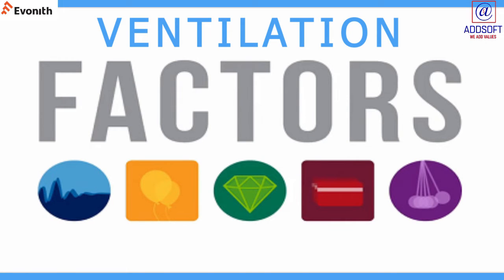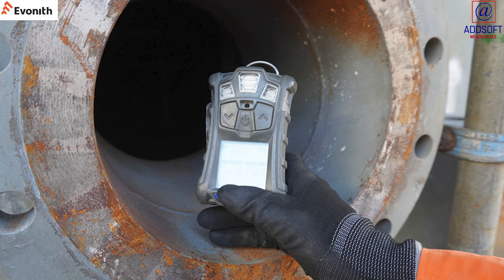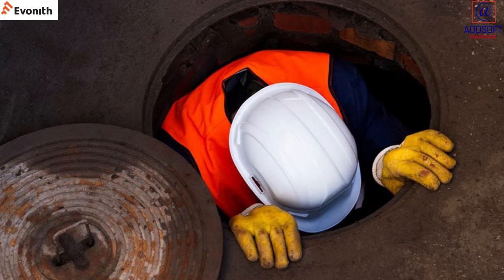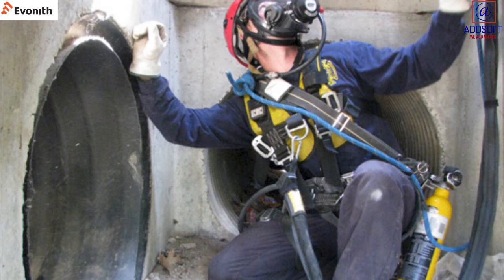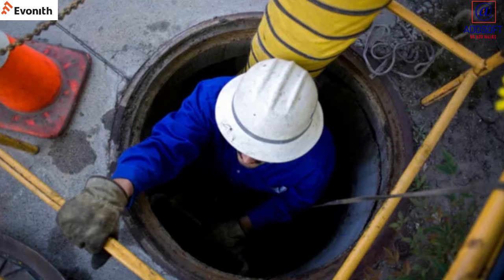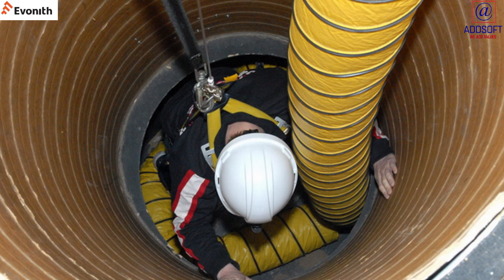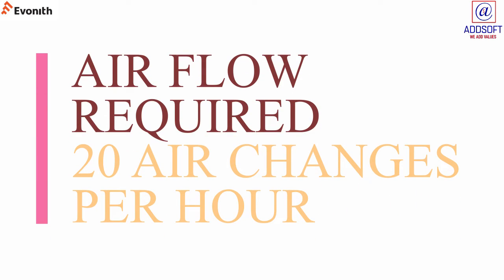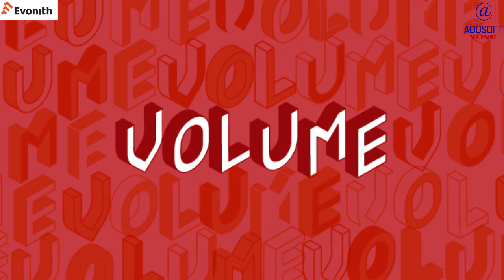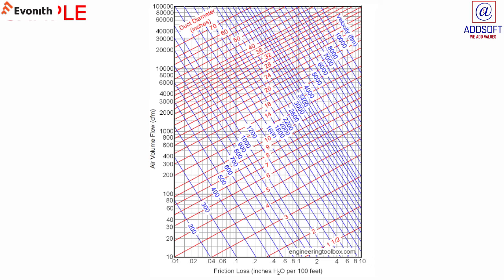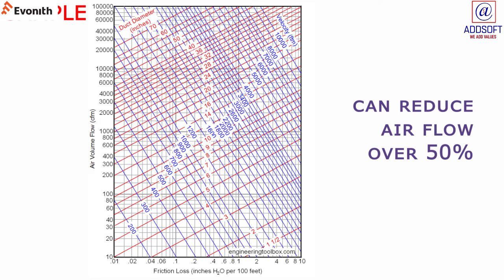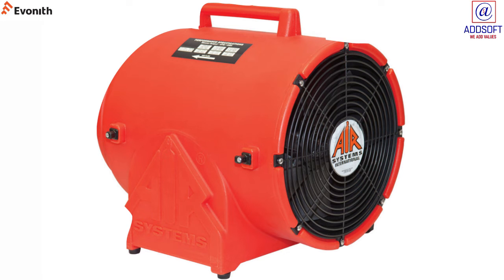Ventilation factors. Job details: atmospheric hazard, size of space, contaminants' density, how fast it's created, how much space is available for vent. Equipment: airflow required, 20 air changes per hour; volume required, breeze to ensure comfort. Duct friction loss can reduce airflow over 50% in 15 feet of duct. Fan performance: design, weight, sound, power.